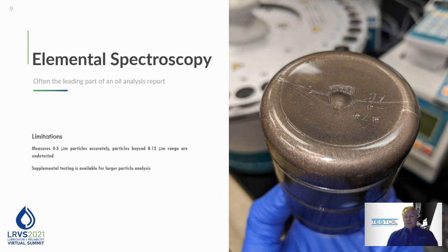Well, wear metals should be at or below clearance sizes. And most clearances, dynamic clearances, are generally under 5 microns. The contaminants that we're most concerned about causing that wear also would have to be near clearance sizes, which again would be under 5 microns. The additives are on a nanoscale, so they're generally an order of 1,000 times smaller than 1 micron. So yes, they're all measured. So that 0 to 5 range, as limiting as it sounds, is actually not a very bad thing.